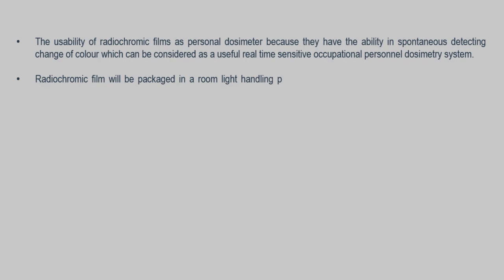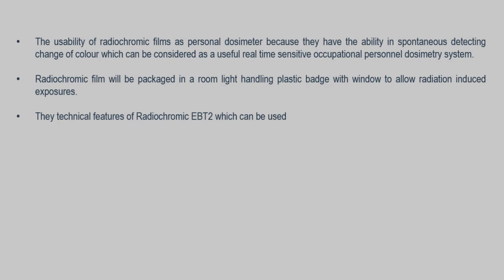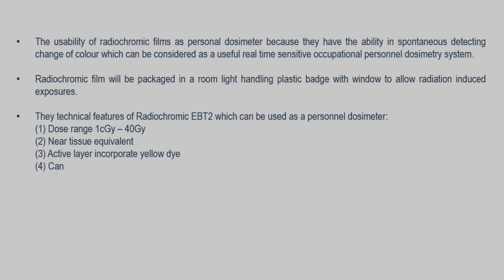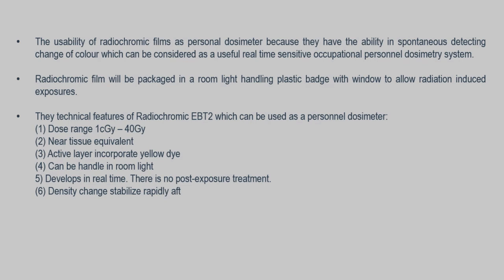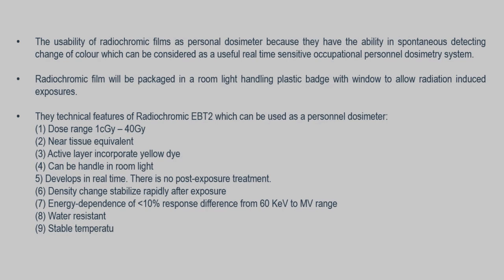These are the technical features of the radiochromic film EBT2 which can be used as a personal dosimeter. The dose range is from 1 cGy to 40 Gy. It has a near tissue-equivalent active layer incorporating yellow dye. It can be handled in room light. Development is in real-time as there is no post-exposure treatment. The density change stabilizes rapidly after exposure. The energy dependence is below 10% with a response to doses from 60 keV to megavoltage range. It is also water-resistant and stable at temperatures up to 60 degrees Celsius.